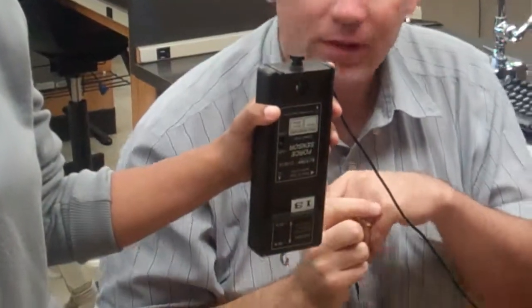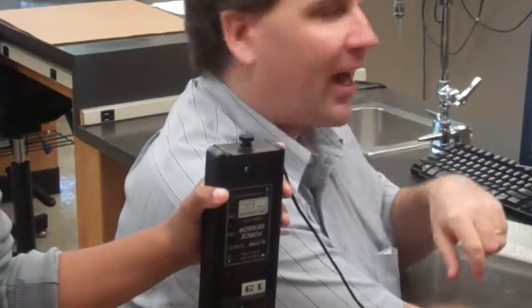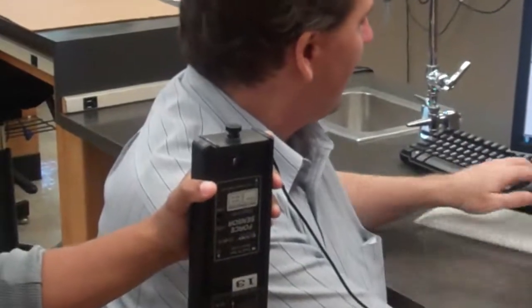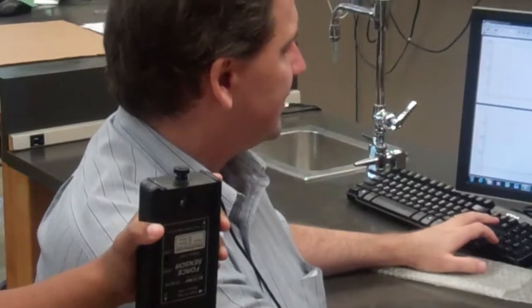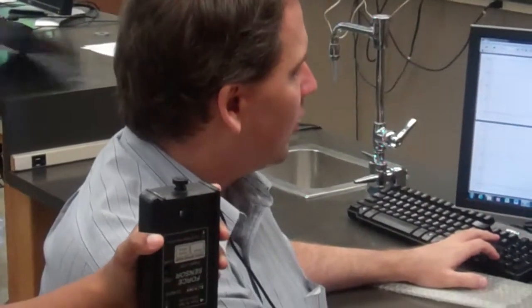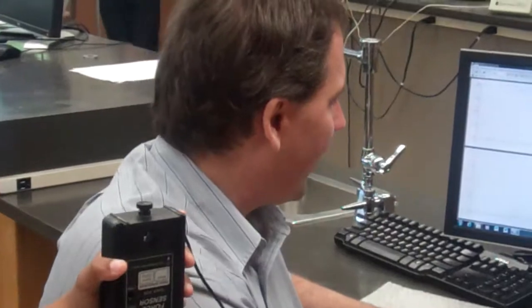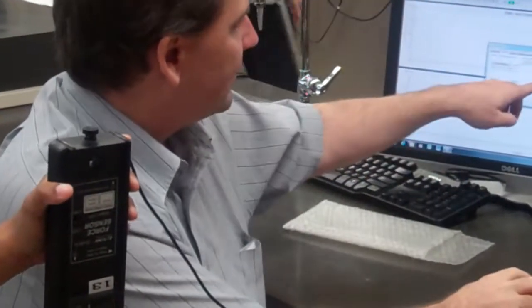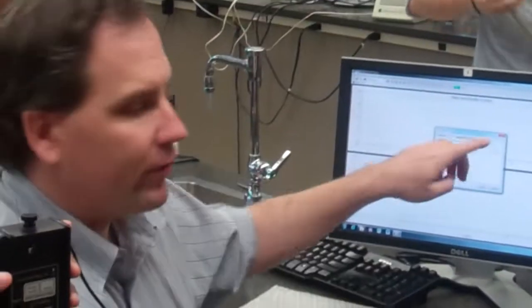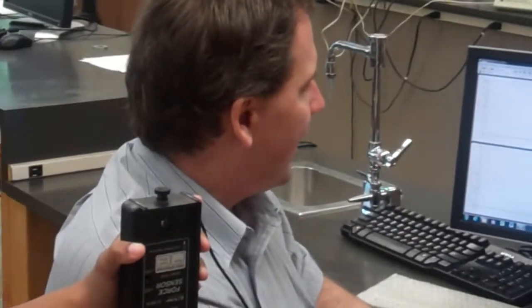We can use that. So we'll do it. We'll hit the button that says calibrate now. And it says enter value in data units. So it wants how many newtons we are applying to it right now, which is 0. Tell the camera. 0. That's better. All right, and then if you look up here, it's got a voltage reading of 2.5 volts. That's good. We hit keep.